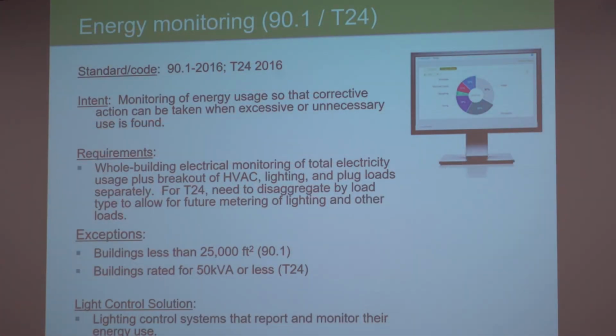Energy monitoring is a requirement in ASHRAE 90.1 and California Title 24, but not in IECC. This is another one that didn't make it into the IECC code, so you don't have to worry about it if you're doing IECC. But basically, whole building electrical energy has to be monitored, and you have to break out HVAC, lighting, and plug loads separately, okay? And technically the requirement in California is to disaggregate the wiring so you can do monitoring in the future if you want, all right? And it's only for the larger buildings or the large electrical rating buildings.